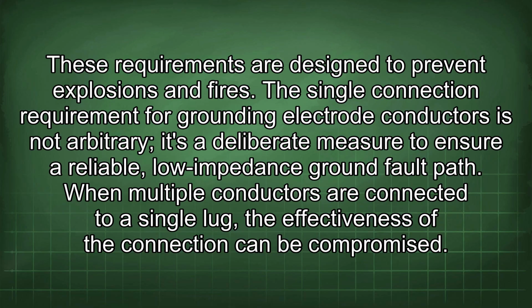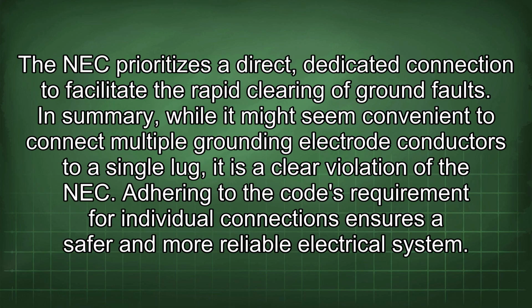The single connection requirement for grounding electrode conductors is not arbitrary, it's a deliberate measure to ensure a reliable, low-impedance ground fault path. When multiple conductors are connected to a single lug, the effectiveness of the connection can be compromised. The NEC prioritizes a direct, dedicated connection to facilitate the rapid clearing of ground faults.